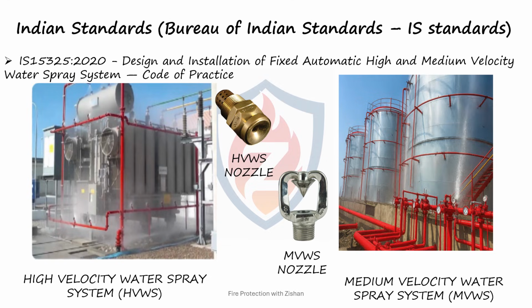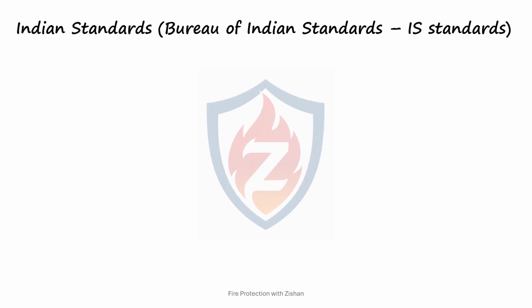High-velocity water spray systems are mainly used for direct fire suppression, while medium-velocity water spray systems are generally used for cooling and exposure protection. By following the requirements of IS 15325, these systems can provide reliable protection for critical industrial assets, minimize fire damage, and enhance overall plant safety. This makes water spray systems an essential component of fire protection in power plants, oil and gas facilities, petrochemical industries, and other high-risk environments.